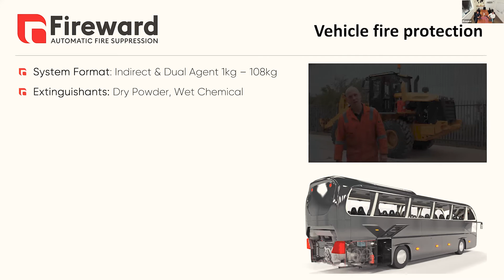We can have these in indirect, as we mentioned earlier, and dual agent, sized from 1 kilo to 108 kilo, with multiple cylinders attached. We use dry powder and wet chemical, and when we look at a dual agent, they are combined, providing the fast fire knockdown of the dry powder, which you saw in the video at the start, and then the rapid cooling from the wet chemical. As you will see in the video we're going to play, we had a GoPro inside of that engine.